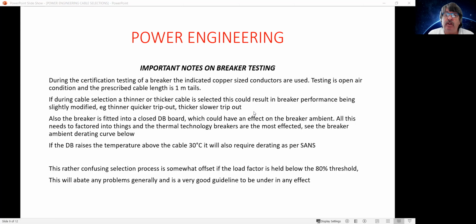Now, these tests on the actual performance criteria, they've done this in open air, I think, which does complicate matters slightly, because they'd all be eventually put into a panel board, as we said. But you can't standardize on a panel board. There's no such standardized panel board in existence. So the tests are done on the circuit breaker in an open air condition.